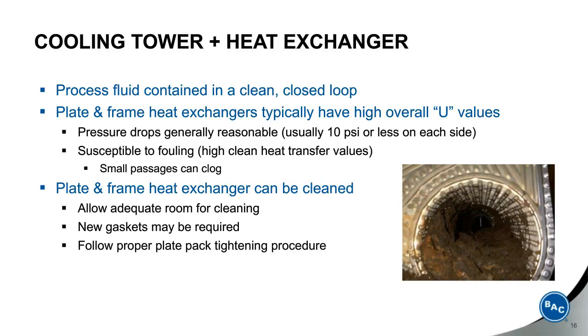These plates are also very tightly packed, about 1/8 inch apart, so they are susceptible to clogging. So you need to make sure you have proper strainers in front of the heat exchanger to avoid that. You can see a photo there of an inlet to a plate and frame heat exchanger pack that became clogged with dirt and debris. Now, the plate and frame heat exchanger can be cleaned.